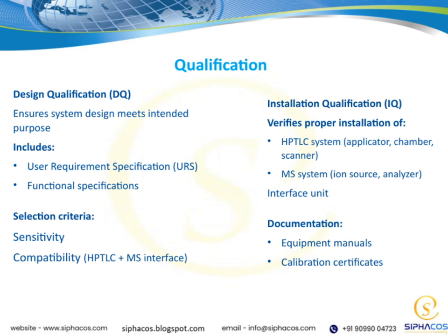Moving on, design qualification, or DQ, is about making sure the system's design aligns with its intended purpose. This includes defining clear user requirement specifications, or URS, so we know exactly what the system needs to do. We also specify functional requirements, ensuring the design meets those needs effectively. When selecting equipment, we focus on critical criteria like sensitivity, how well the system detects what we need, and compatibility, especially between the HPTLC and MS interface. Ensuring these components work seamlessly together is vital for reliable results. So, in summary, IQ confirms proper installation, documentation validates everything, and DQ guarantees the design is fit for purpose. All these steps are essential parts of establishing a robust, compliant analytical system that supports accurate and reliable data.